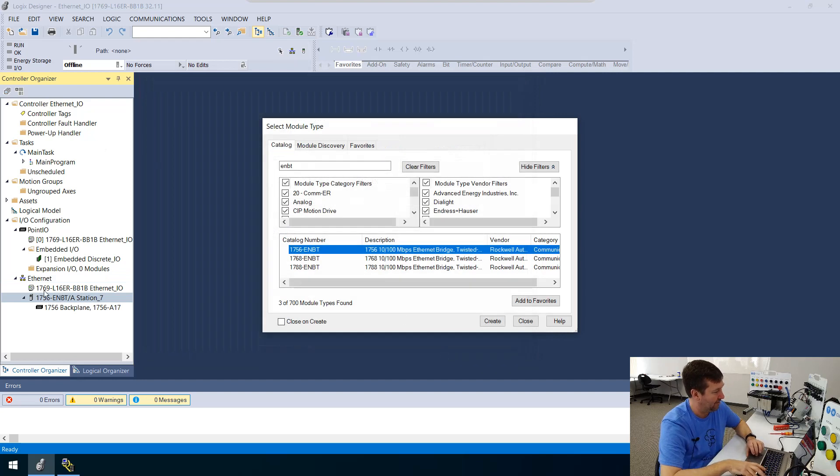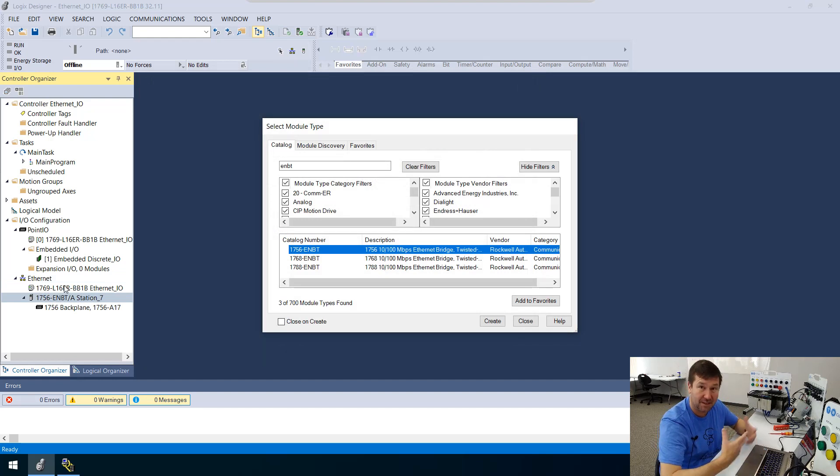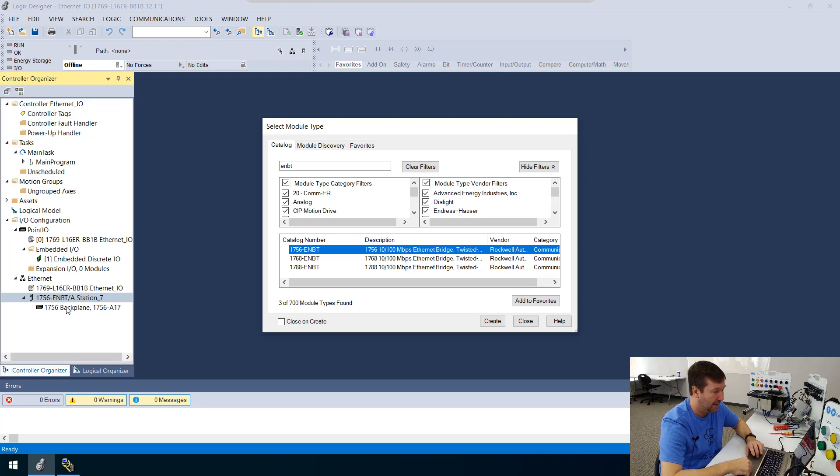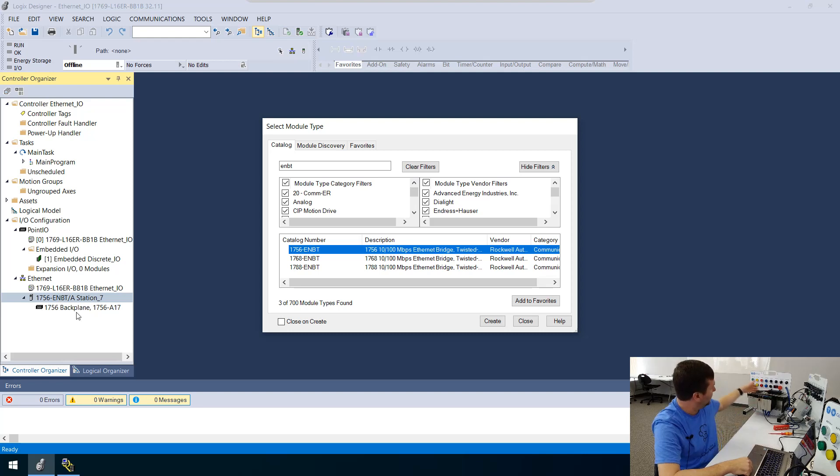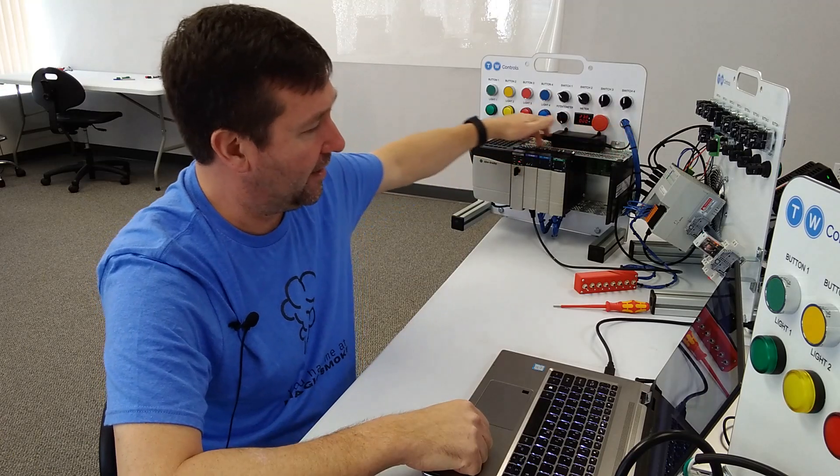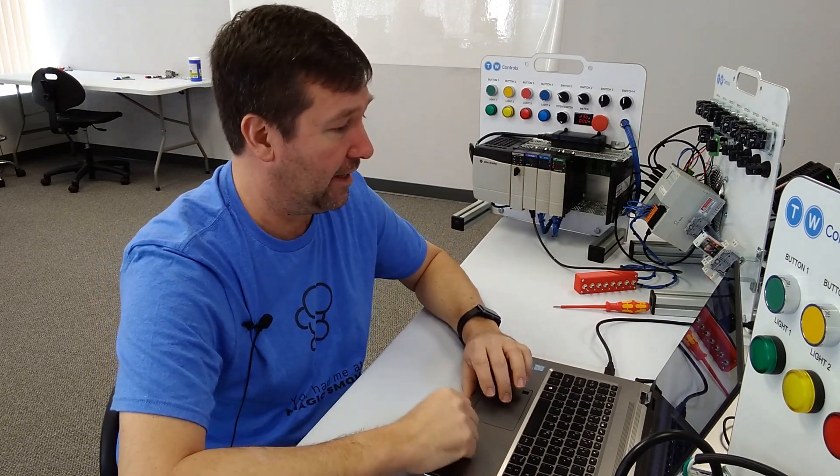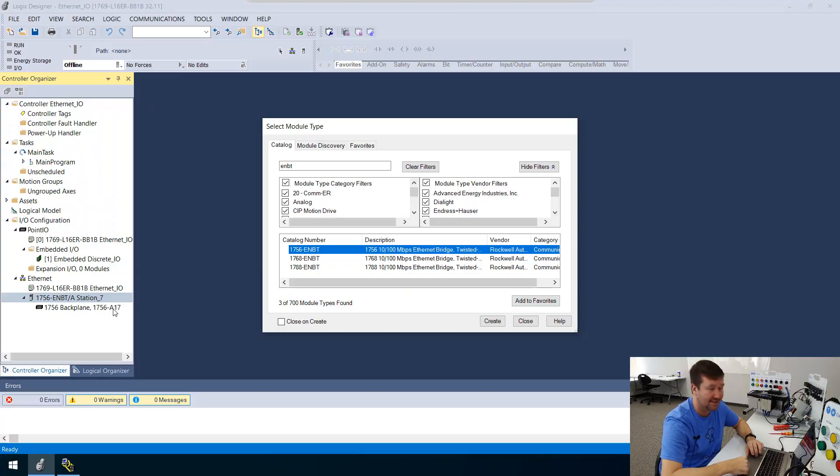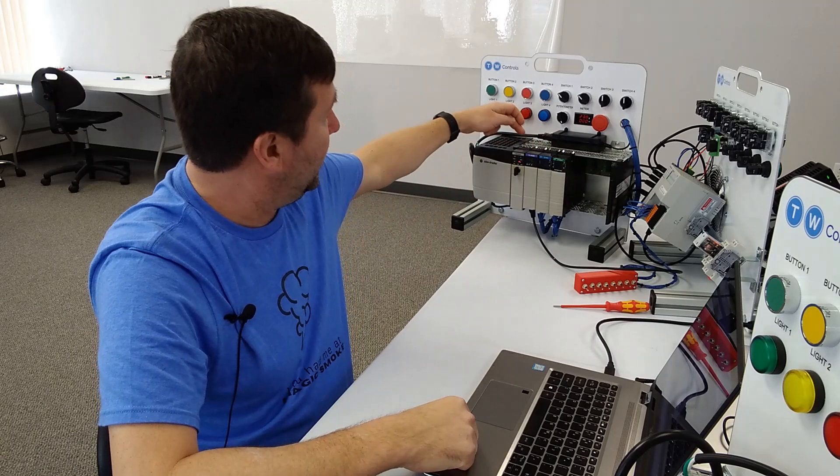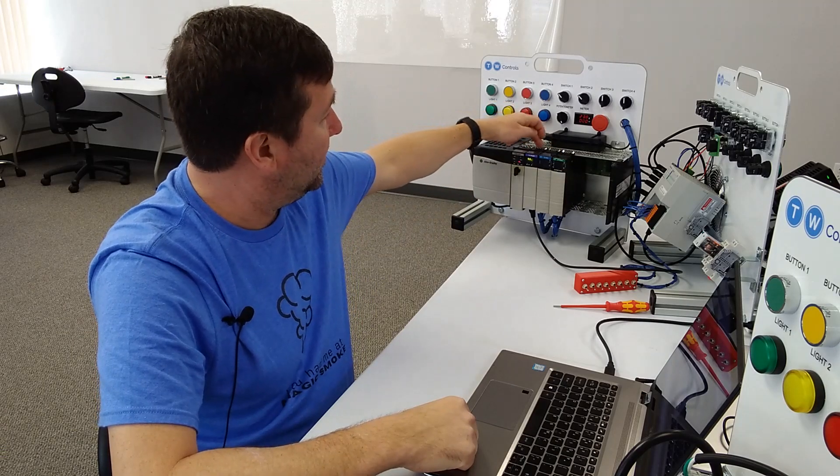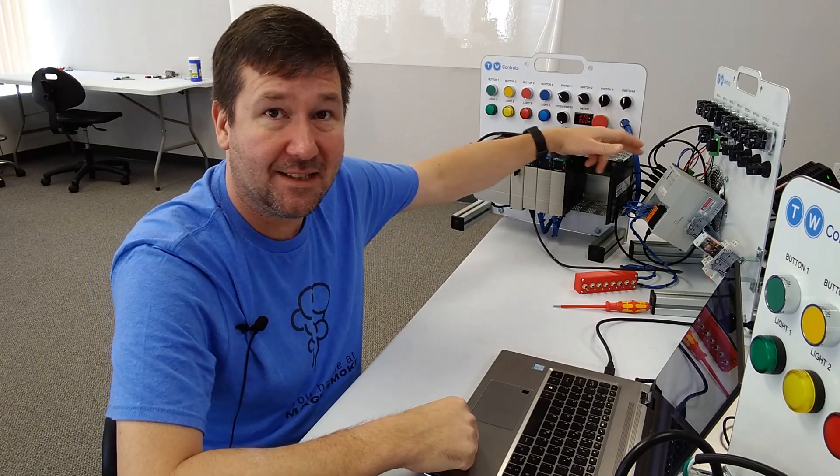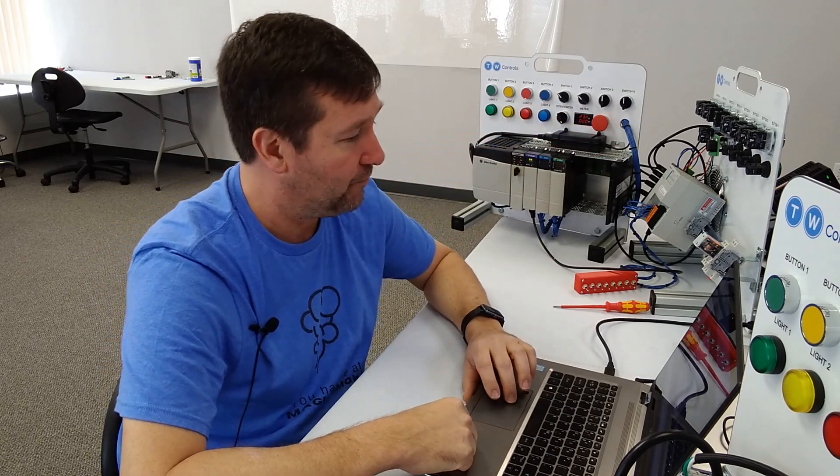And now on our IO configuration here, we can see there is the 1769 L16, which is what this program is written in. And then we have a 1756 ENBT. And then inside of it, we have its back plane, which is this chassis right here. Now, I made a mistake when I configured this because see, it says it's an A17 chassis. Well, no, that would be the number of slots. This is not a 17 slot chassis. This is a seven slot chassis.